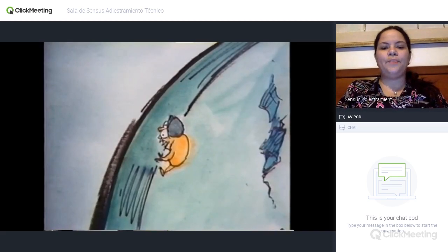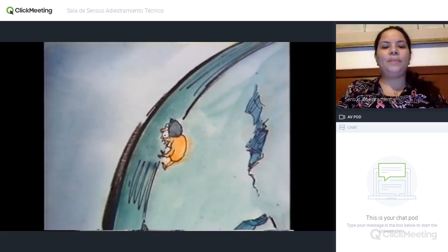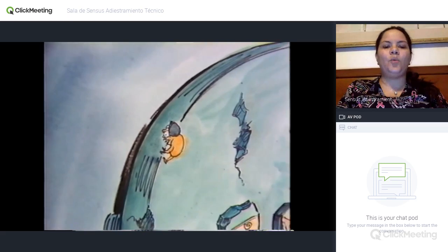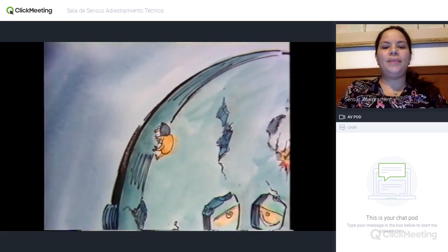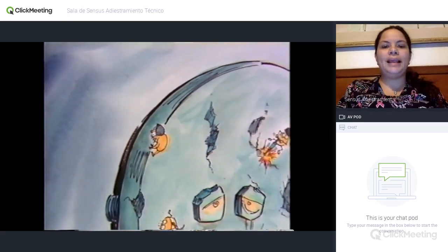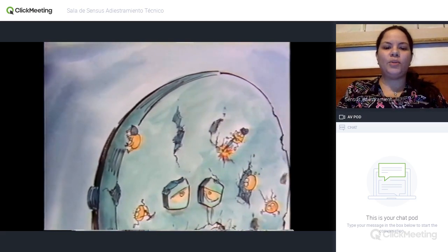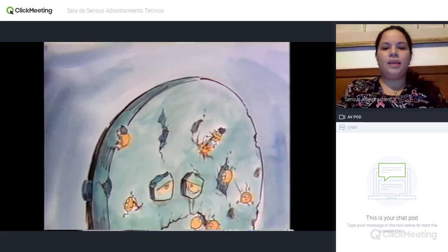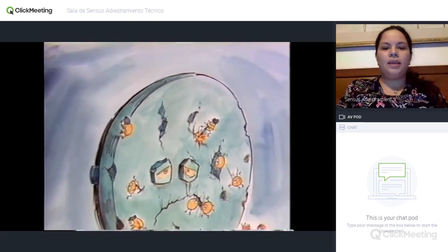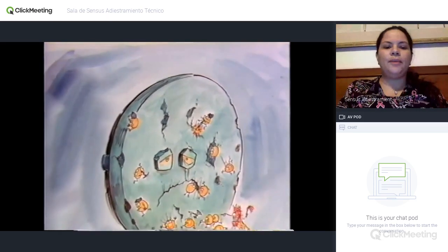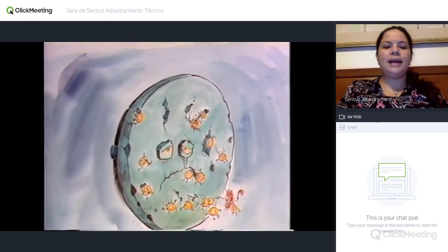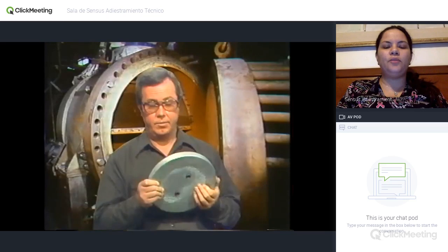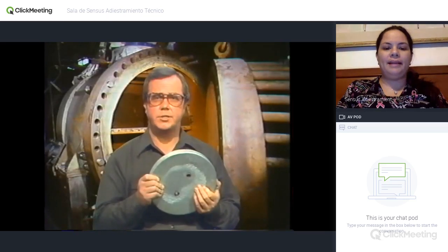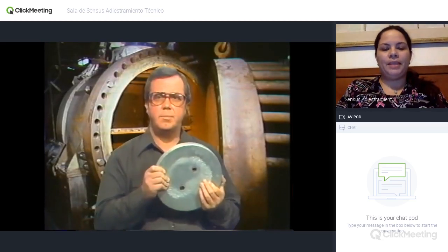They're called sacrificial because they are eaten away by corrosion rather than the metals of the heat exchanger. When they're worn down so far, they have to be replaced. Just when is usually a matter of judgment. But one rule of thumb is to replace them when they're more than 50% eaten away, or when they are in danger of coming loose from their mountings. Replacement is a straightforward job of just bolting a new one in the place of the old one, and you're done.